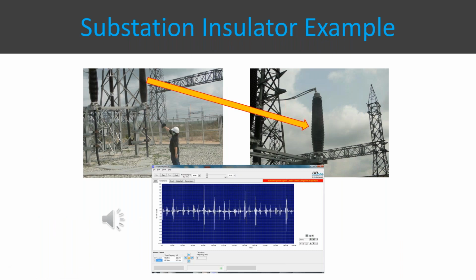As I mentioned earlier, you can have corona or tracking problems. Here's an example of an insulator in a substation, in Thailand. As you can see, it's a little more than just corona, it's the beginning of tracking. This is actually a brand new facility, but it had been so long since they installed these until they actually did the startup of this power plant, that the moisture in the air, the salt air, everything got to the insulators and coated them. So when they fired it up, a lot of them already had issues. They could address these issues because they weren't that severe, but with a simple scan, in this case from 15 feet away, we were able to pick up whether there was a problem or not.